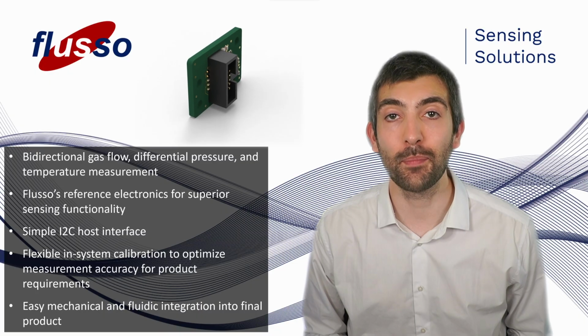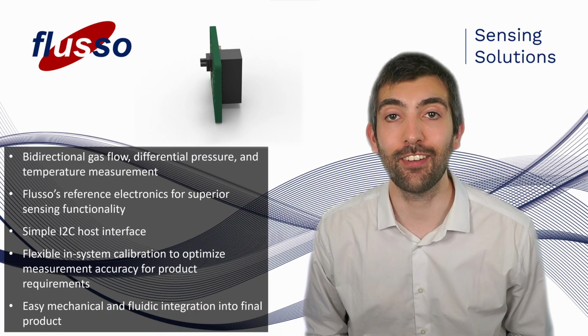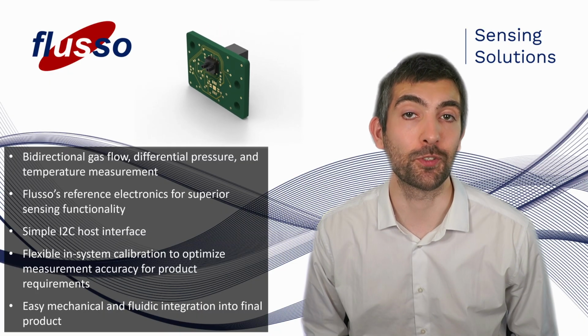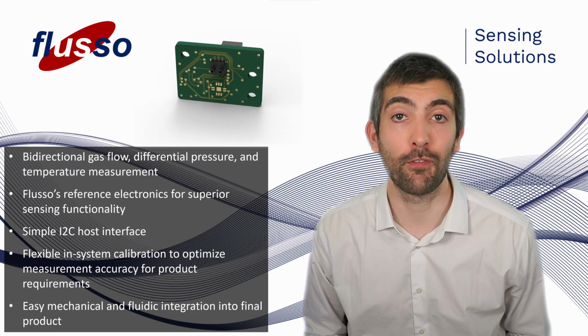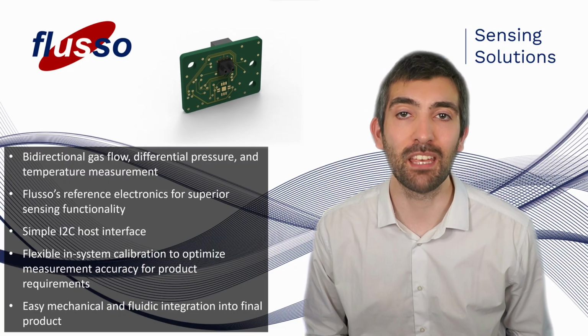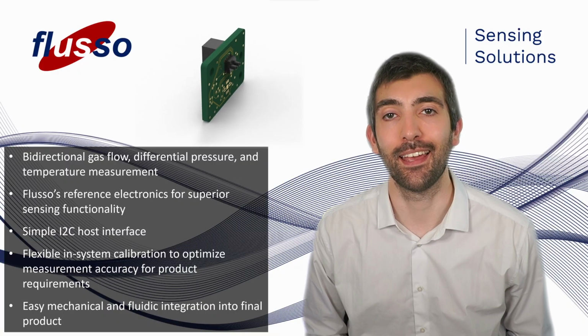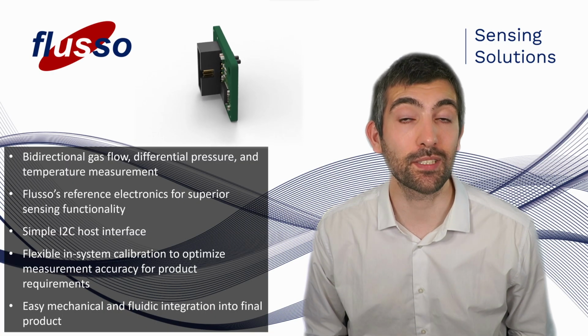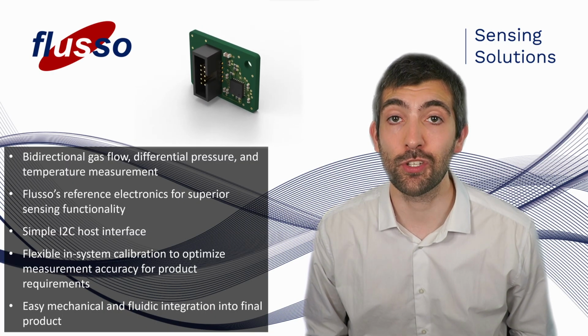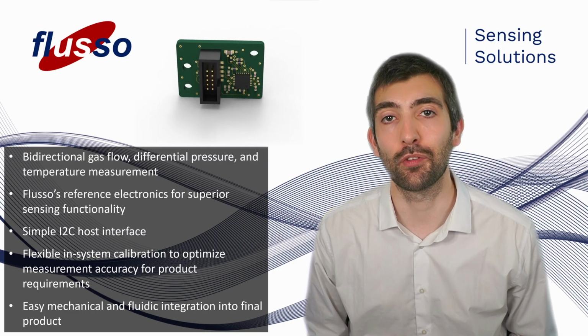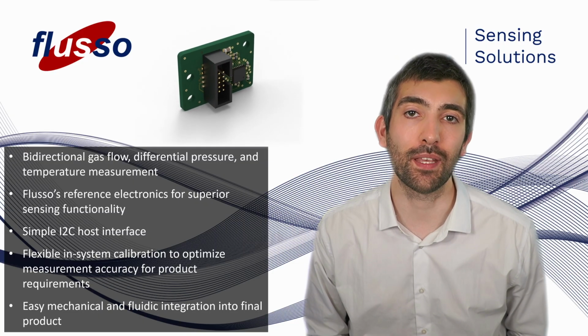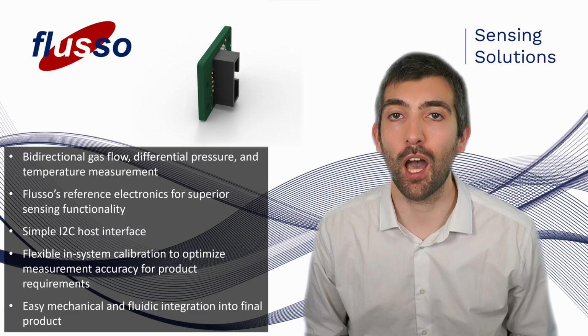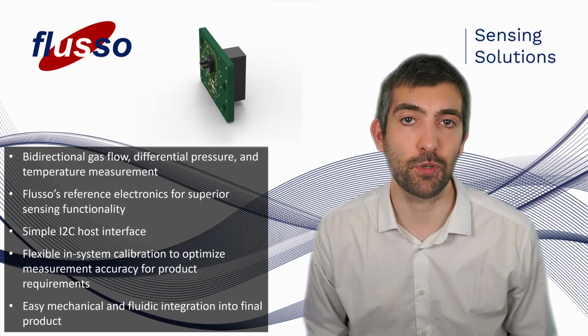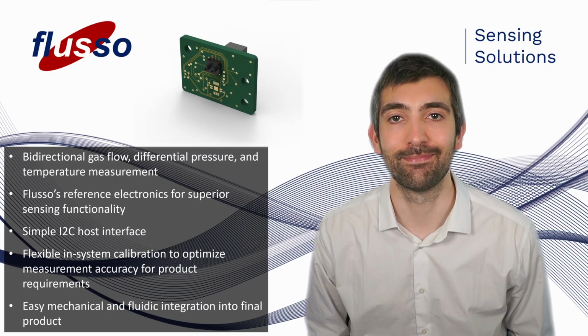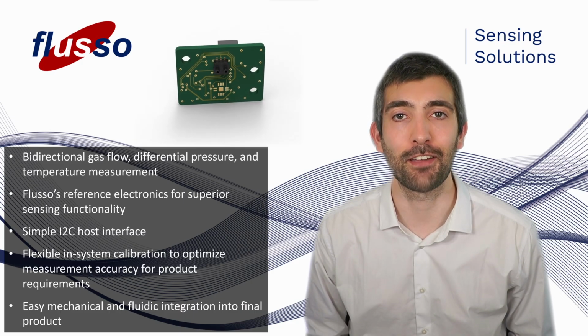In this video, I'm going to be giving you an overview of our new FSE-112 flow sensor module that you can use to measure mass flow, volumetric flow or differential pressure in both the forward and reverse direction in your application. We're going to start with an overview of the module on the bench, we're going to look at how to install it into a flow path, and I'm also going to take you through the calibration procedure so that you can be up and running, measuring flow with exceptional accuracy as quickly as possible. Let's not waste any more time, let's dive right into it.